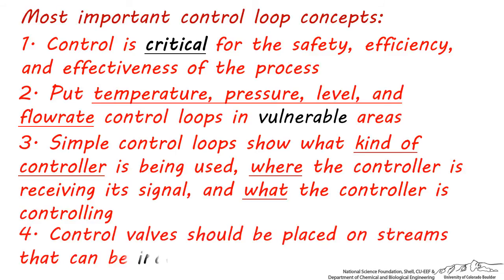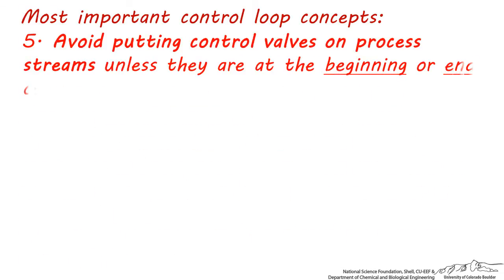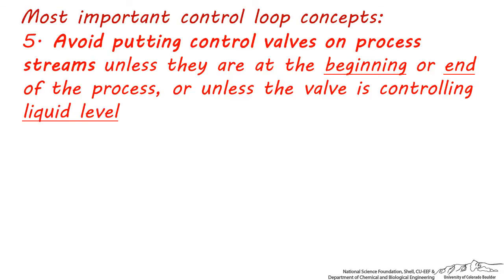Remember that control valves should be placed on streams that can be independently adjusted, such as the flow rate of fresh feed coming from a storage tank, or the flow rate of steam or cooling water going to a heat exchanger. Related to this point, avoid putting control valves on process streams unless they're at the very beginning or end of the process, or unless the control valve is controlling the liquid level in a flash, distillation column, or vessel.